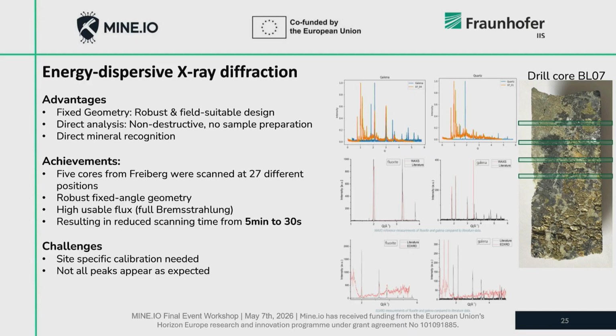We scanned several cores from Freiberg at different positions, using the fixed angle geometry and the high usable flux. With the energy dispersive approach, we could reduce the scan time from 5 minutes to about 30 seconds. But there are also some challenges. We found out that we would need a site-specific calibration, and because of orientation challenges, not all peaks that help to identify the actual minerals appear as expected. So there's still some work to do in this case.